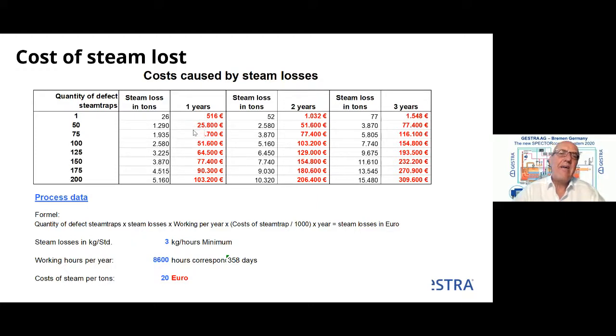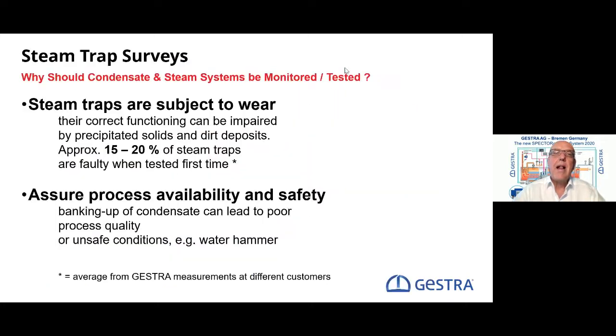Just to say, steam trap survey. Should I do a steam trap survey every year, every 6 months, or every 3 years, as we asked before? Then we make, after a certain time, a survey when a customer has planned one which was not done in the last 3-5 years. Then we find out that around 15 to 20% of the steam traps are already faulty. If we make an annual test, then we reduce this number to 5 to 10% faulty steam traps, mostly caused by dirt and solids and corrosion problems in the customer plant.